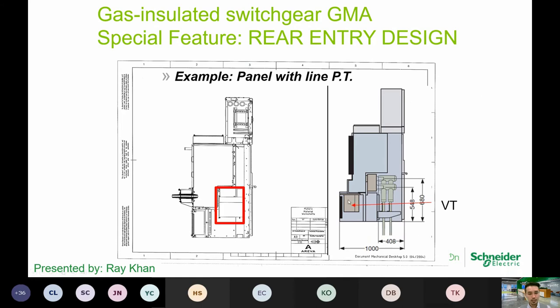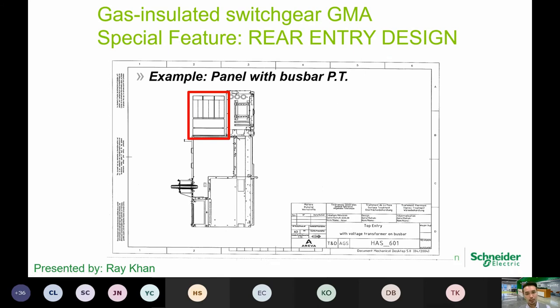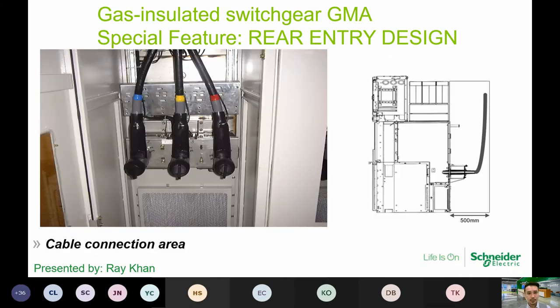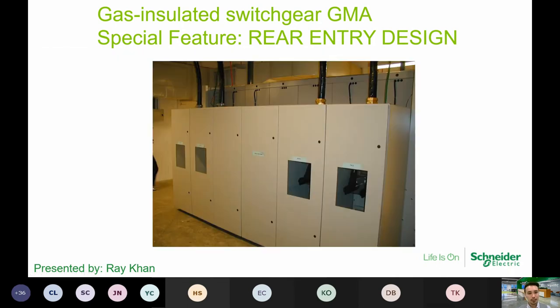Okay, so in this picture you can see that it is at the rear, which gives the users rear access. Okay, so also we have the VT at the top. Commonly the one at the top is for the bus bar. This slide shows that in the event your project requires a cable from the top, you need to cater a spacing of 500 mm in depth, right? So how it's done is actually quite simple. They put in these panel plates to cover up, and then it enables the cable to come down from the top in here. So once it's done up, it will look like this for a rear entry design.